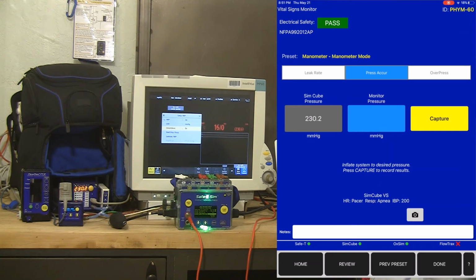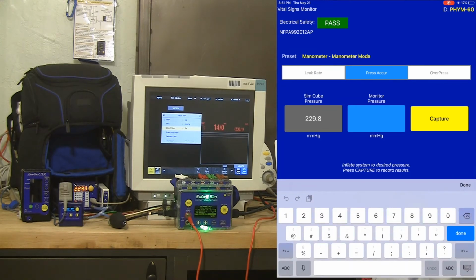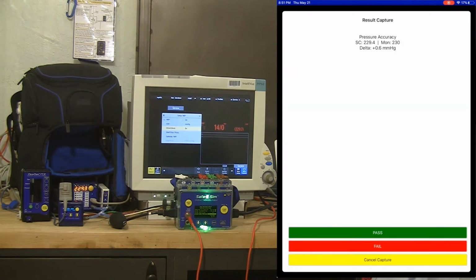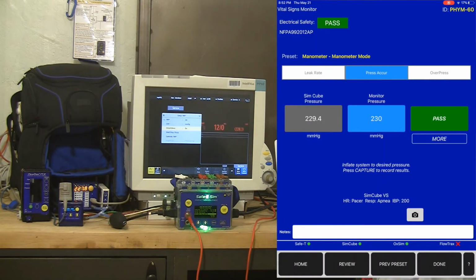I'm going to leave the system inflated at 230 millimeters of mercury or so, and I'm going to type in the pressure seen by the vital signs monitor and hit capture. Now I've got a pressure accuracy result based on the SimCube manometer and the transducer in the NIBP circuit. On the capture screen, we're actually showing the delta as well as both the SimCube pressure and the monitor pressure. So we can see a delta of 0.6 millimeters of mercury, so those two transducers are very close, and we got a pass.